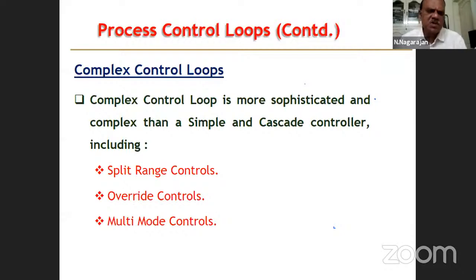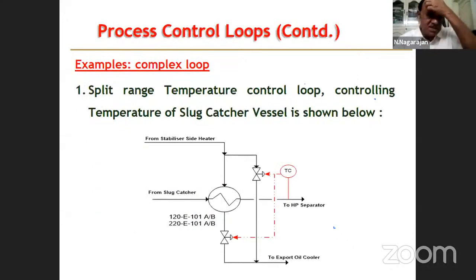Override control, sometimes we want to override a particular control, you want to bypass. It's something like a bypass control. Multi-mode controls, it's again the number of parameters are more and the variables are more, then you use the multi-mode controls. We'll see some examples here. Split range control is, this is nothing but hydrocarbon getting heated in a heat exchanger.